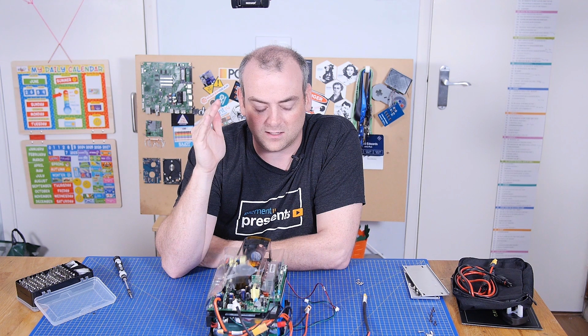Industrial UPSs are designed normally to look after computer systems, so they do what's called a double conversion. A double conversion UPS takes AC input, inverts it to DC, charges the batteries at all times, inverts from the batteries on the DC circuit back up to AC, and it's that AC that runs the mission critical equipment. Now, that's great - it provides, basically, if mains power fails, it's totally transparent at the point of use. The computers, the servers, whatever they are plugged into it, don't even know the power has changed because they're always being powered by an inverter.